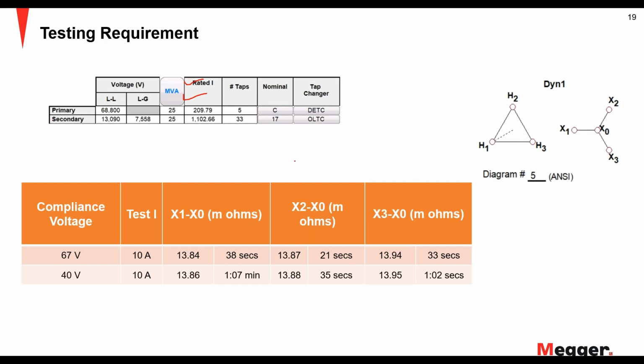It actually depends on the rating of your transformer itself. You have your line-to-line voltage. In this case, it's 68.8 kV to 13.09 kV. And based on the MVA rating, I have my rated current primary and rated current secondary in this case. And that's why I'm using 10 amps current on both the sides.